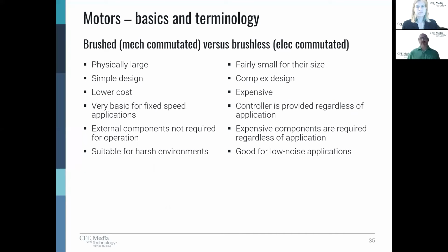So you do have to communicate that with your client and say, I want to use ECMs for this application, but just know that when you have to replace it, it's going to be a lot more expensive than you're used to. The benefit is that I get really good speed control, and the speed control is actually inherent and built in.